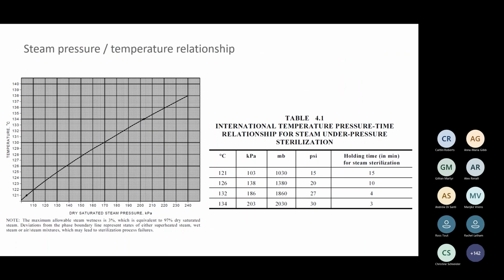So this is what I was talking about, the steam, pressure, temperature relationship. This is very important because just because your sterilizer might not reach 134 degrees, it may still be sterile if your holding time is at 4 minutes. So if your sterilizer is processing at 132 degrees and it's holding for 4 minutes, then your loads are going to be okay. This is important if you have an auditor come in and say your machine hasn't reached 134 degrees, so it's failed. You need to go back and look at your holding time and make sure your holding time has covered you for the process.